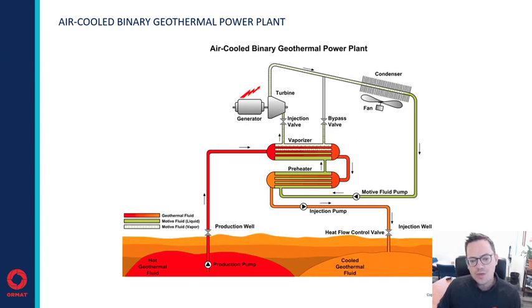Now what we do is take that exhaust gas and send it into the air coolers or condenser. The condenser cools the liquid back down, it turns back into a liquid, and we have a motive fluid pump which pumps it back into the preheater. So the geothermal fluid, the brine if you will, and the working fluid never touch. They are simply in a tube and shell heat exchanger exchanging that heat.